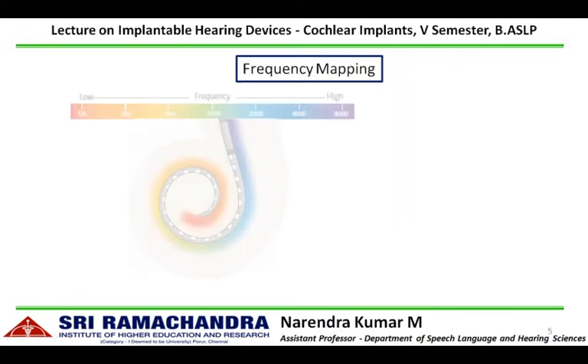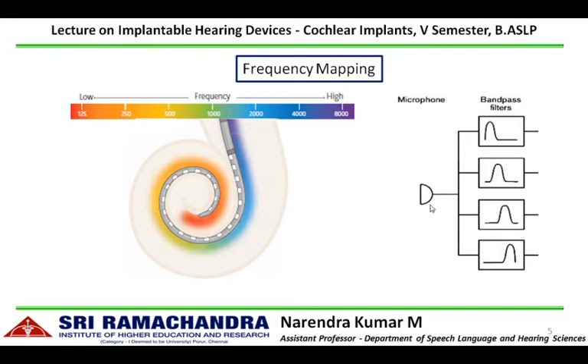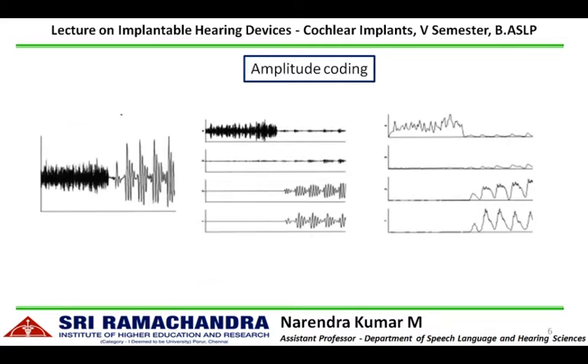Frequency mapping is controlled by the intracochlear electrode array using multi-channel implants. Each electrode contact area has its own bandpass filter, so the microphone picks up the sound energy and splits it into a series of bandpass filters. The output of these bandpass filters is delivered to the cochlea through the appropriate electrode contact area. Low frequencies are mapped to electrode contact regions that reach the apical end of the cochlea, and high frequencies are mapped to the basal end, thereby maintaining the tonotopic organization of the cochlea.